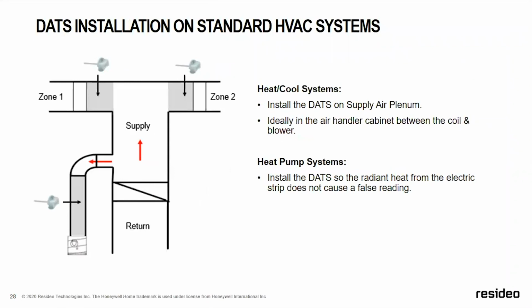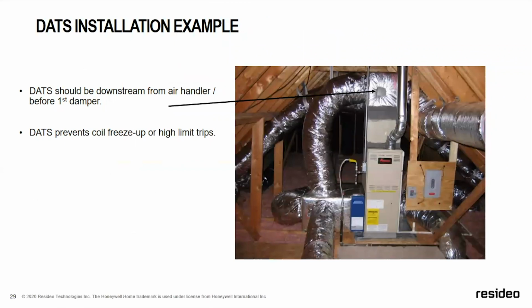Now, in my market, in the Chicagoland area, typically we have plenums that are in the basement that are on average 24 inches high. I like to tell customers, install the discharge air temperature sensor at least 12 inches above the coil so you don't get the radiant fallout, but you're in the main airstream. This is typical of my market. My market may not be your market, so always reach out to your local reps for help in this matter. We are all across the country and Canada. We're all ready, willing, and able to help you design a zoning system. Always remember, it should go before the first damper, and it prevents coil freeze up or high limit trips.